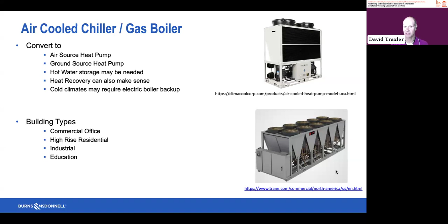In a system like this, you may need to add something like hot water storage. The reason is that in these large multifamily buildings, the warmest time of day for everybody is usually the middle of the day, and that's when air source heat pumps can generate the most heat, but you need the most heat early morning. So you may need hot water storage to store heat from the previous afternoon and use it the following morning when your heat pump capacity is lower, or to offset adding additional heat pumps on the roof. In some instances, if you're in a very cold climate, it may make sense to add a boiler backup, electric or fossil fuel, for those few times a year when it's really cold, which could save significant money in upfront costs and electrical upgrades.